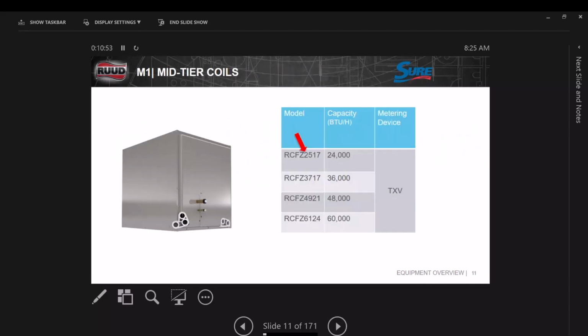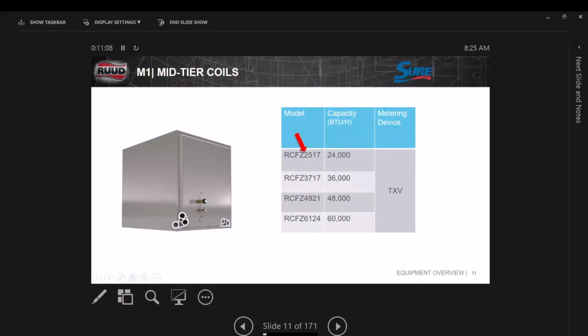On our evaporator coils on the mid-tier, you want to make dang sure that if you're putting in a mid-tier system, that it has the tonnage like this: 25, 37, 49, 61. You remember we used to do that in our product, right? When we were coming up between 13 and 15 SEER units way back when. So if you're putting in a 3-ton and it says 36, it's not the right unit, not the right coil. Okay? So just keep that in mind. The 37, 49, that means it's the high tier stuff. The Z just means it's the new M1 series stuff.